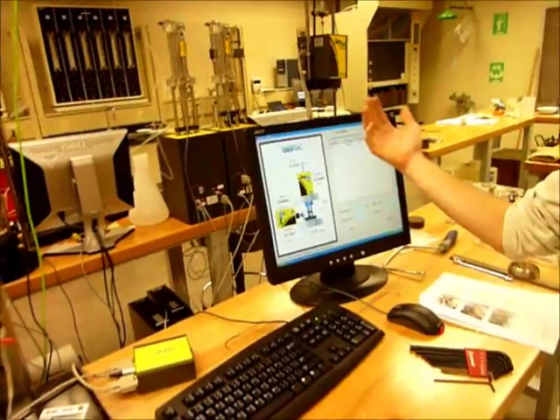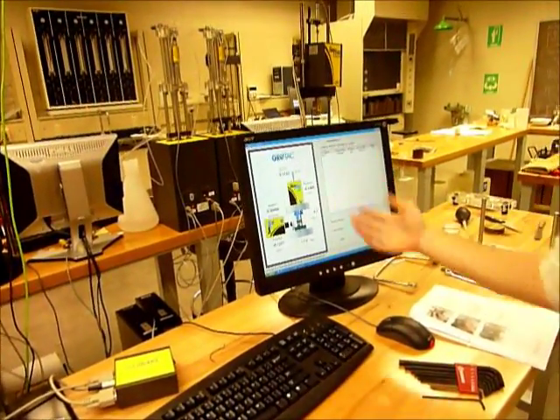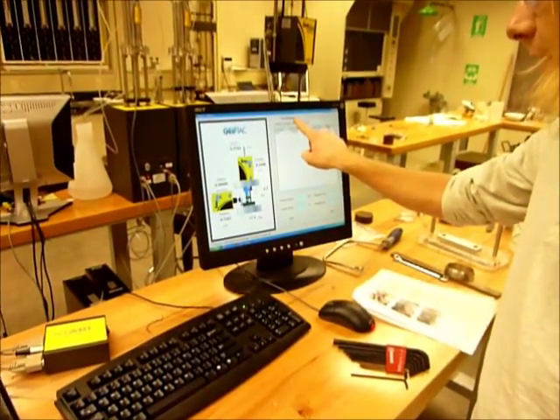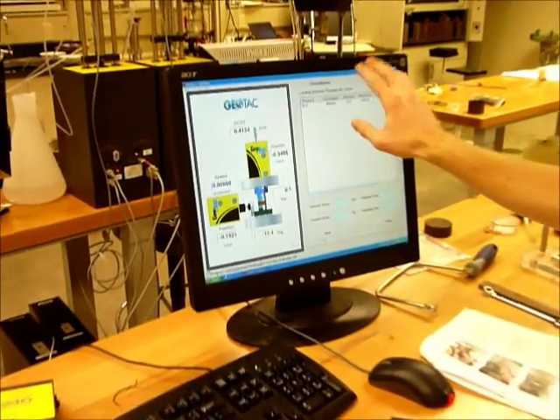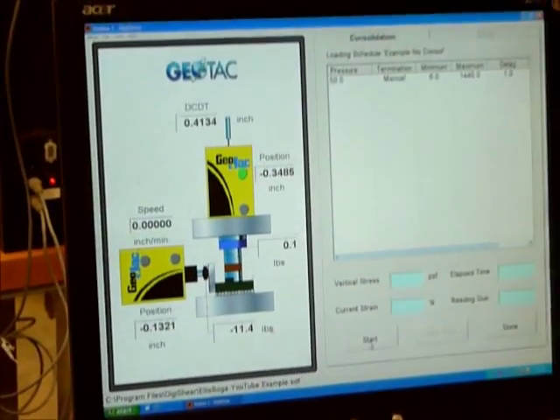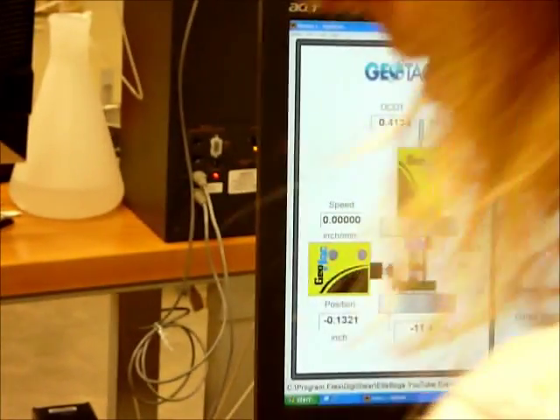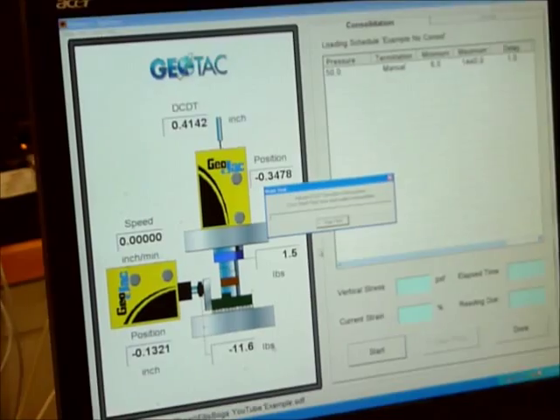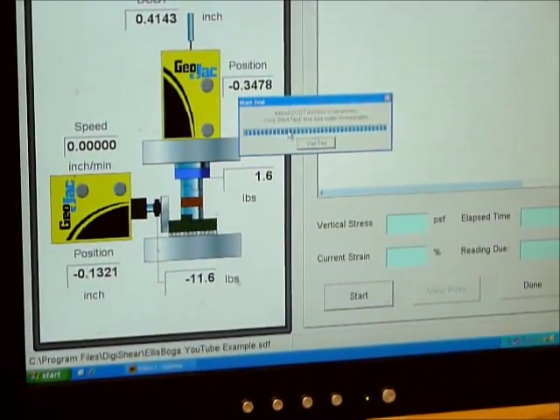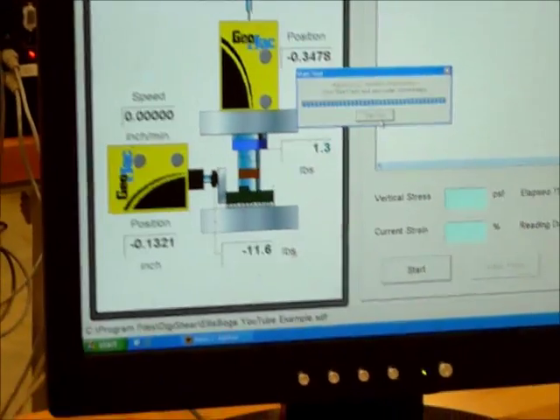Earlier, we put in how we want to do our consolidation, how we want to do our shear. And you can see up here on the consolidation tab, shear is not active right now. But we want to start consolidation. We don't need to remove the rings, the clamping rings for this. Can we hit OK? Hit seating. Start test.